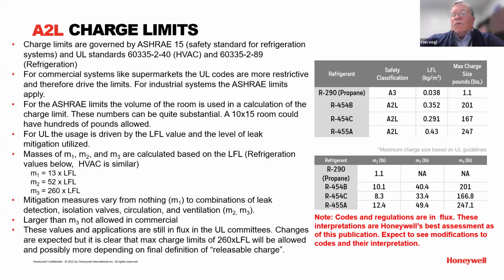Be careful, because let's say you build a small supermarket system or a distributed rack with 455, using 247 pounds, the max. A year later you lose charge and grab a tank of 454C. If you put 247 pounds of 454C in there, you'd be out of compliance because its max is 166. I know this is coming at you fast and seems complicated, but talking to the OEMs, their literature and maybe even apps will be clearer on what you can use and where. It's worth keeping in mind because things happen.